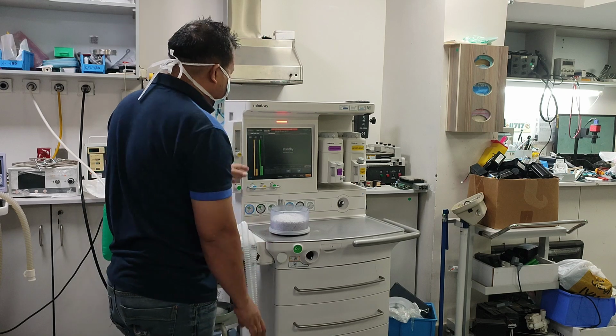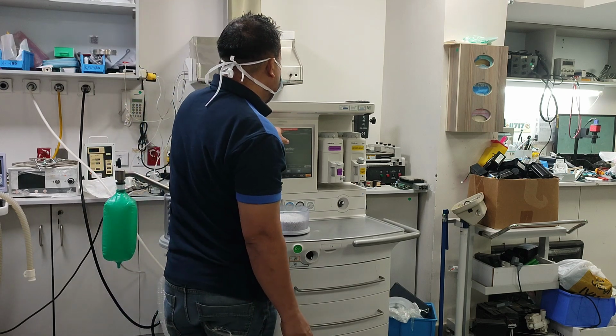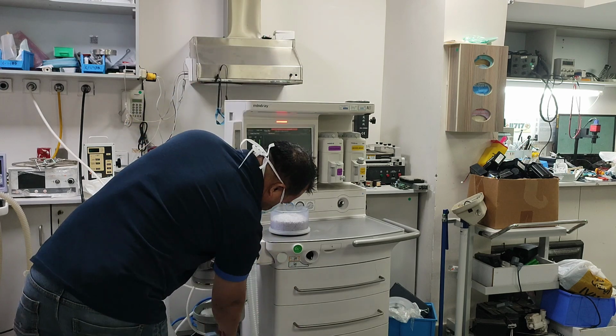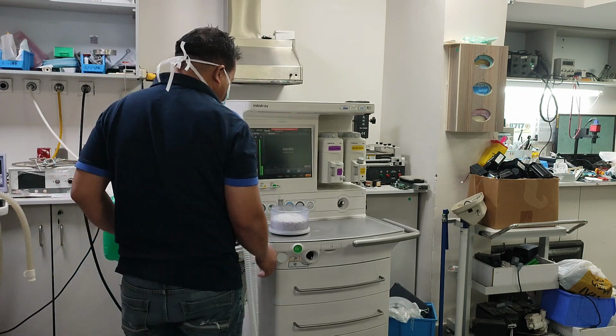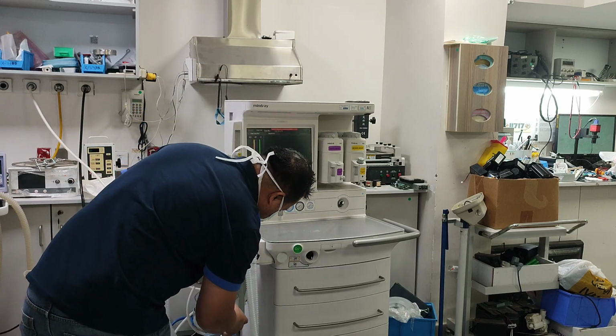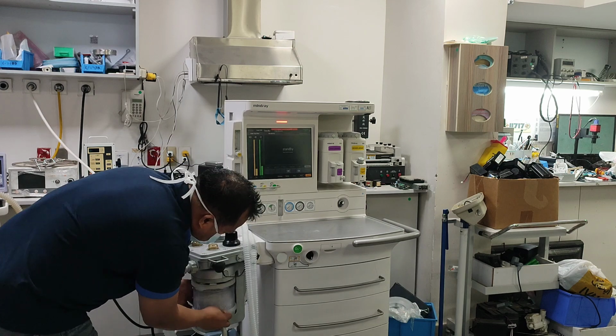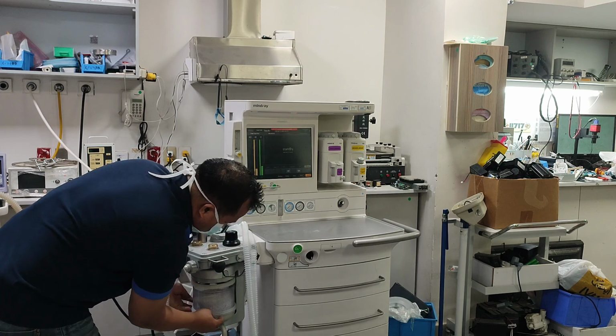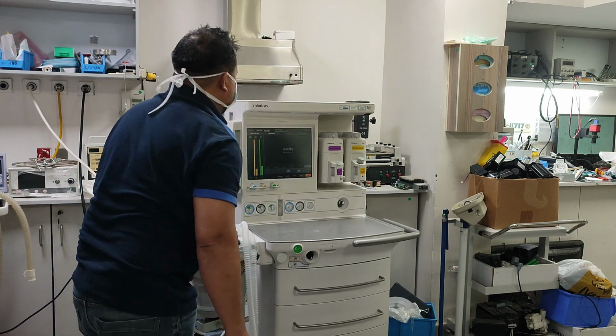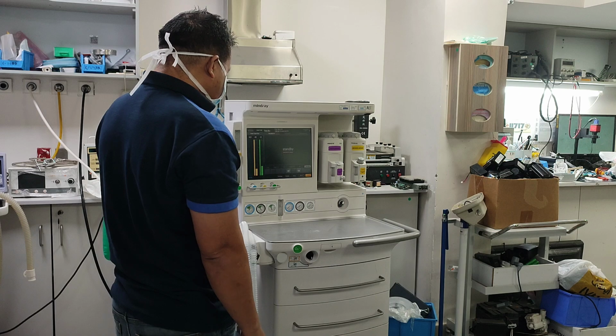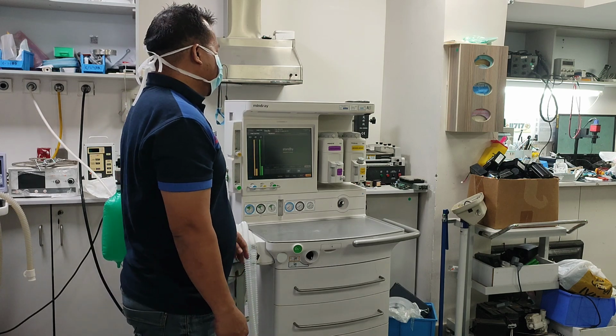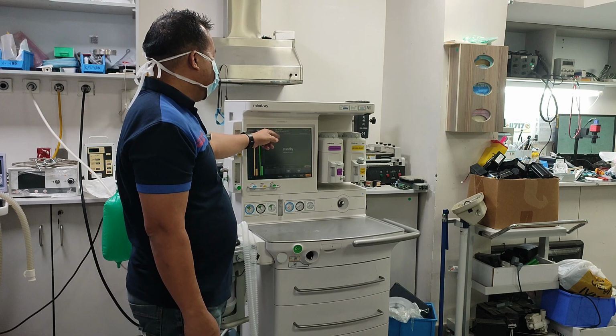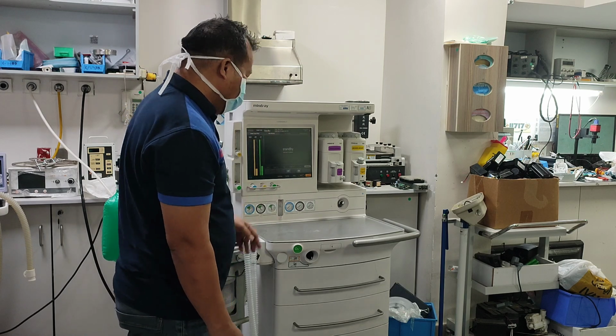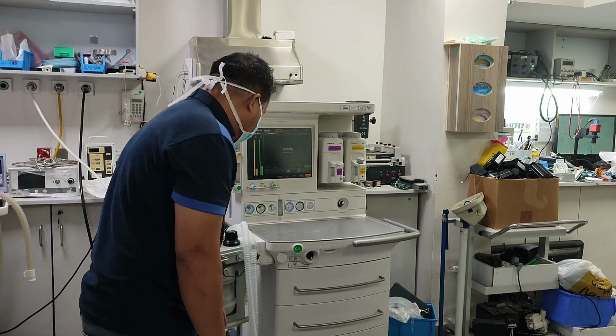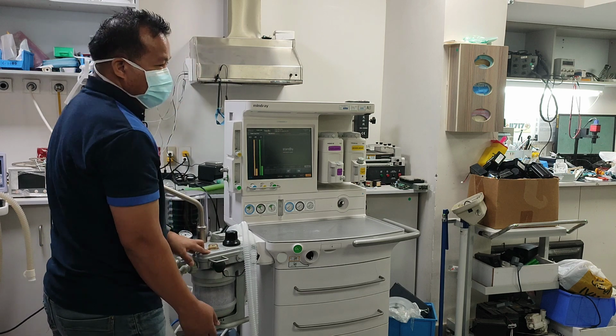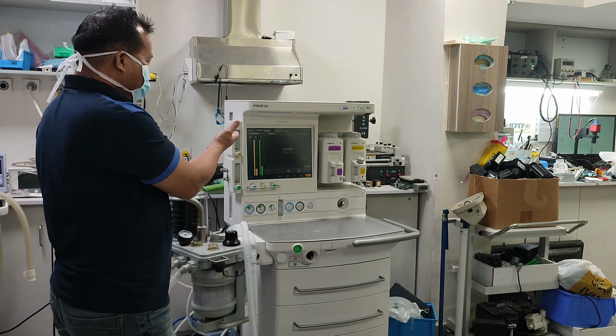Here, once you remove it, there is an alarm. See, the alarm says CO2 absorber canister not locked. So, we remove it. Once you return it, just seat it a bit in the rubber and close it, and the alarm will stop. So once you have an alarm, they will call you, because sometimes the users forget to lock it. There's an alarm on the screen. You should check only this one if there is a CO2 absorber alarm. Because there is a limit switch here, it does not touch, meaning the limit switch is open, so the alarm will appear here.